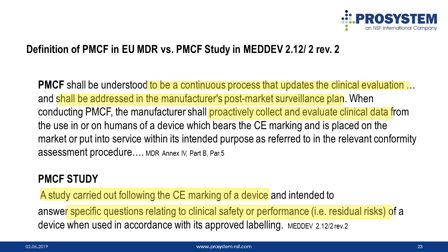When conducting PMCF, the manufacturer shall proactively collect and evaluate clinical data. However, it is important to note that the requirement for PMCF under MDR does not necessarily mean that clinical studies will be required in all cases to collect clinical data, which is what is currently understood as PMCF under the current directives due to the wording in the MedDev guidance document.